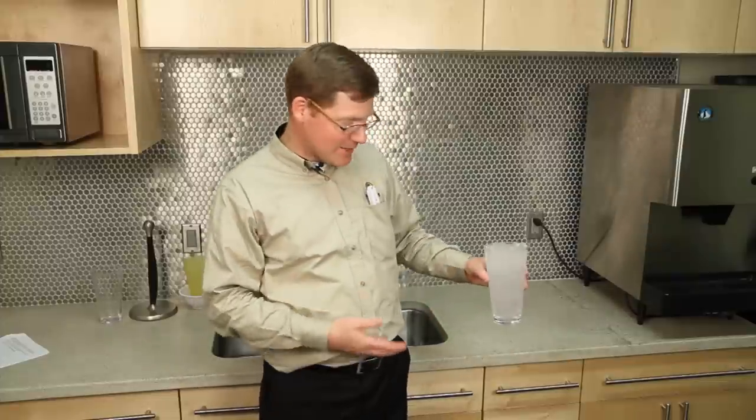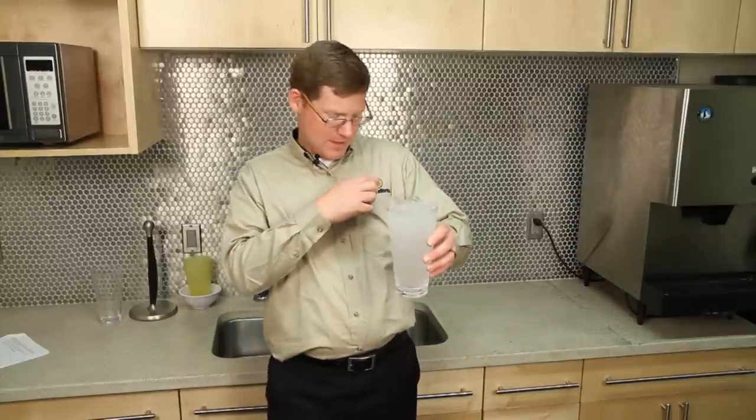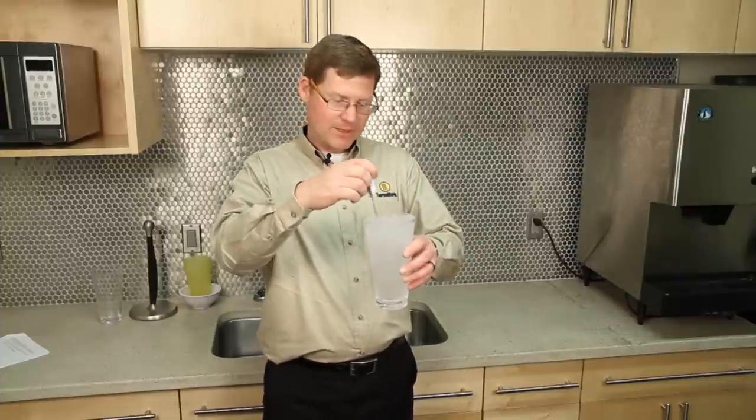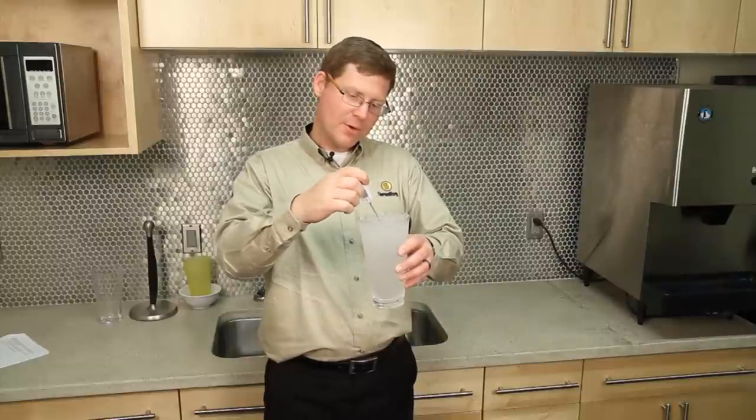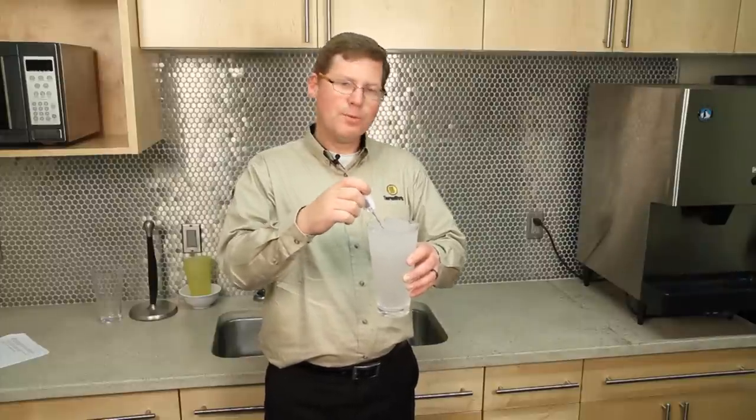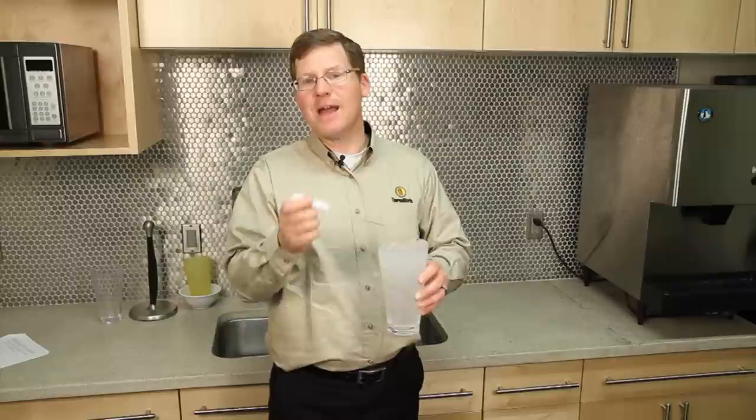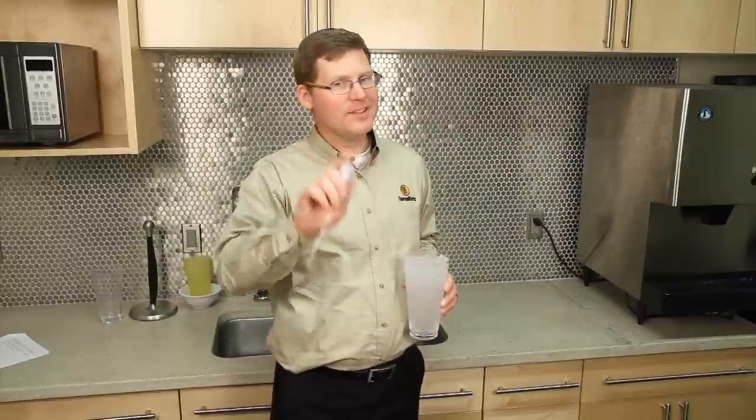So now we've created a proper ice bath. Look at this thing of beauty. We've stirred our probe to take our reading. This thermometer reads 32.5 degrees. Time to adjust, right? Not so fast.